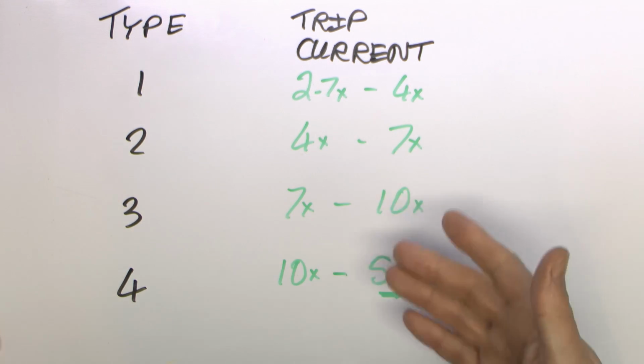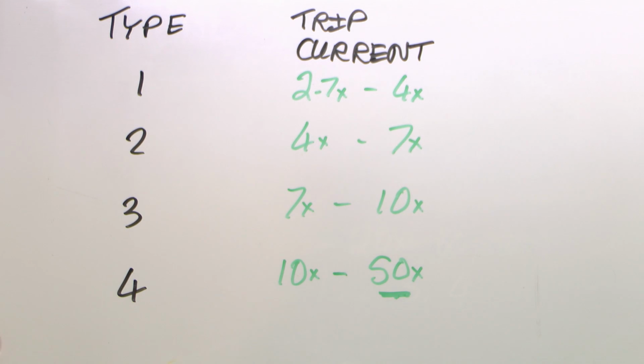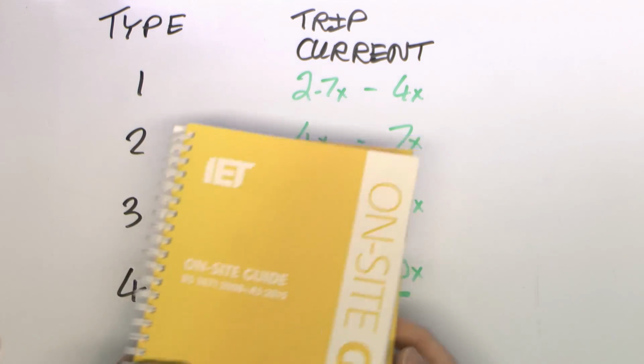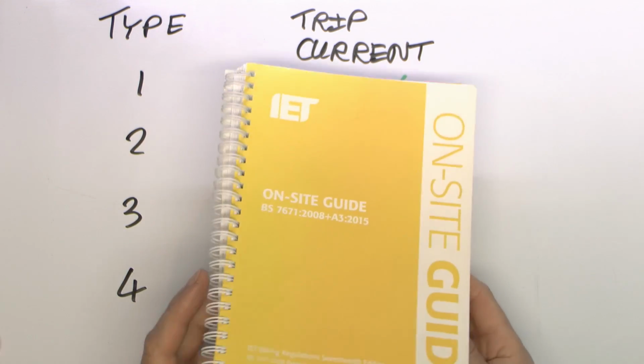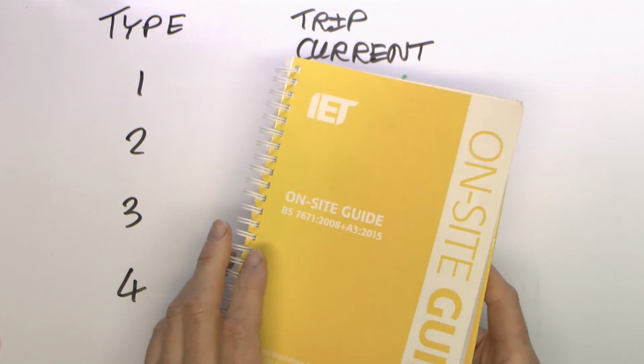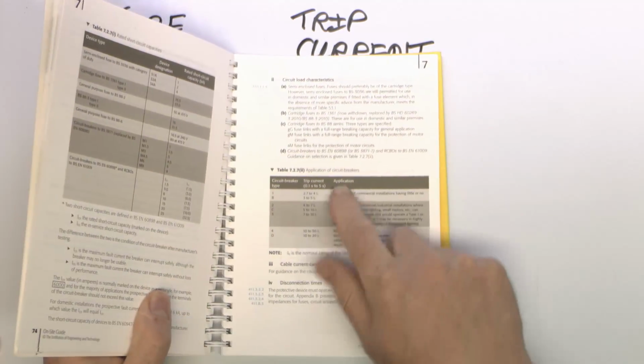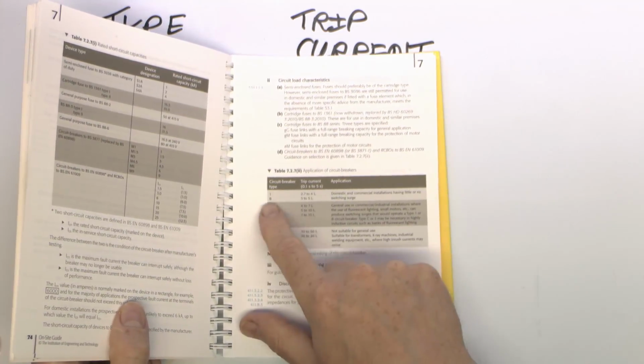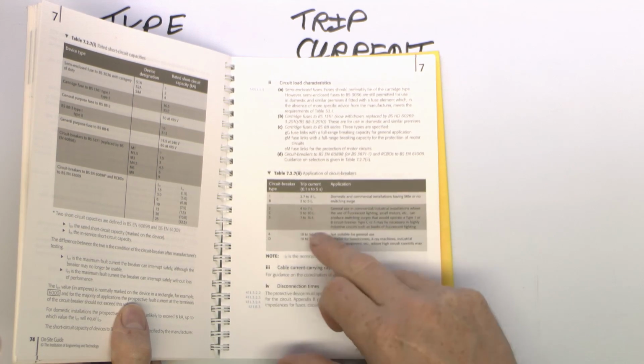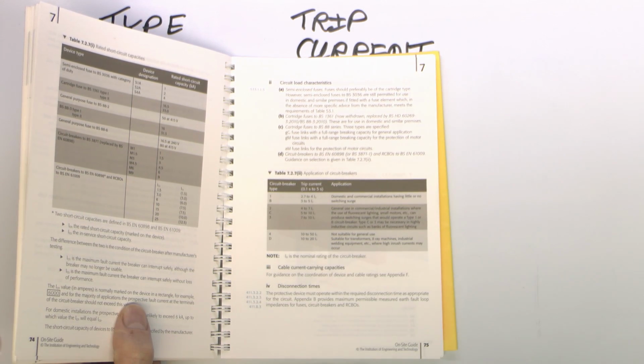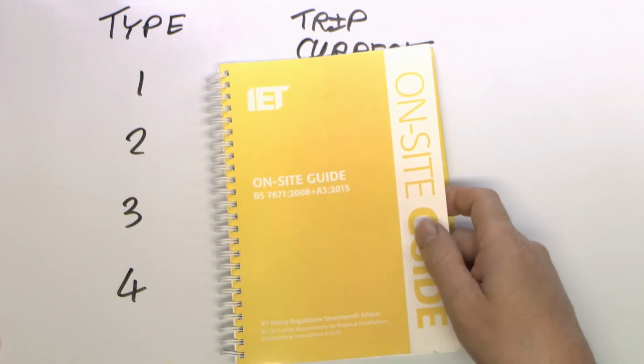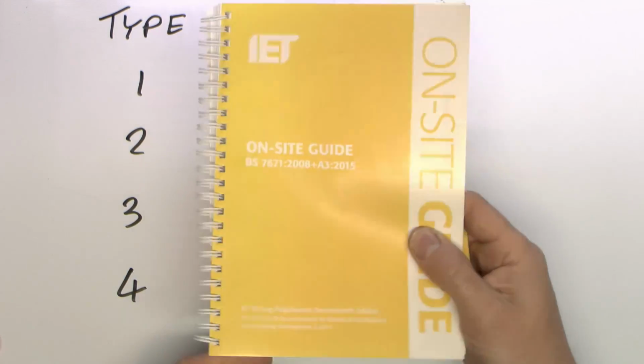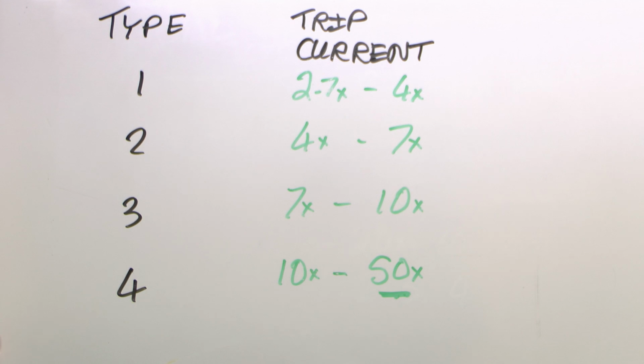Now, if you do forget what these are, because let's face it, you're not going to necessarily remember all of this, then the information can be found. It's not actually in the wiring regulations for these ones. It can be found in the on-site guide. This is the current edition here, the yellow one. And we can see inside here there's a table in section 7, which just gives you the various types there and the actual trip current that you've got. So it's in there in the smaller guide, not in the main regulations. Although, of course, the B, C and D types obviously are, because those are the current ones.